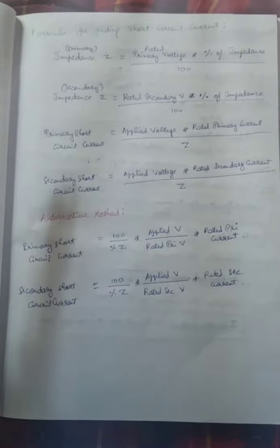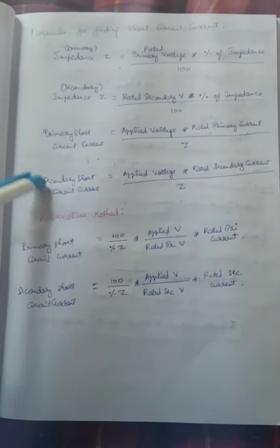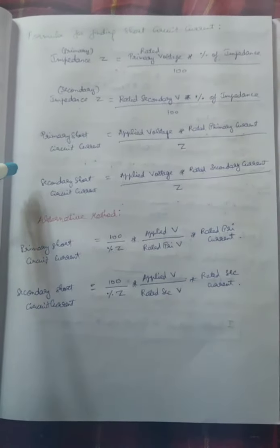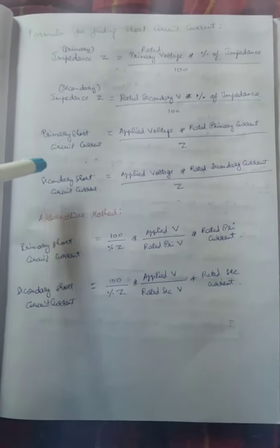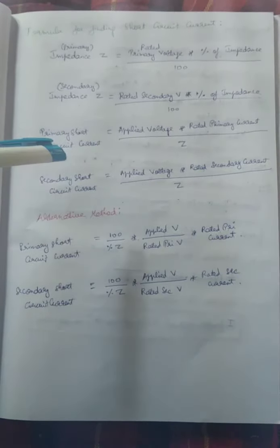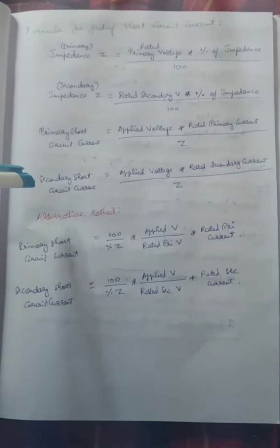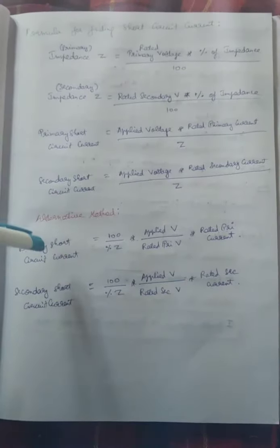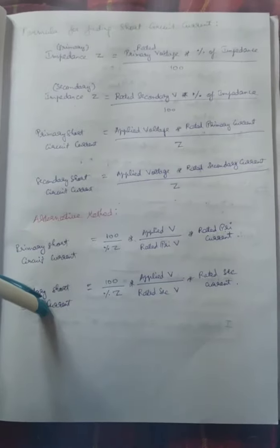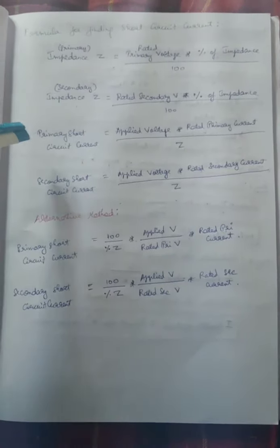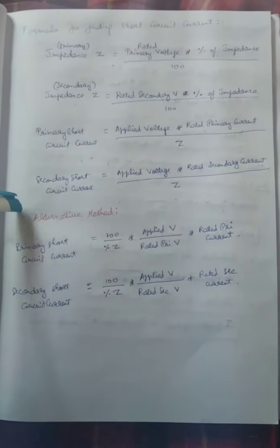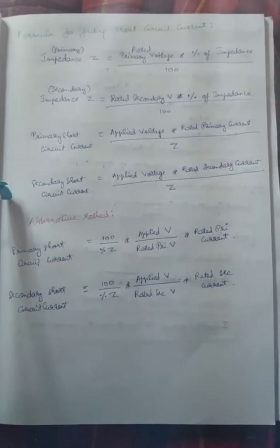going to do the short circuit current, for each tap we need to calculate this theoretical value. If the transformer has 5 taps, in which we are going to inject for tap 1, tap 3, and tap 5: tap 3 will be the nominal tap and tap 5 will be your maximum tap. For these 3 taps the short circuit current is going to take place, so for the 3 taps we need to calculate the theoretical value of your short circuit current.